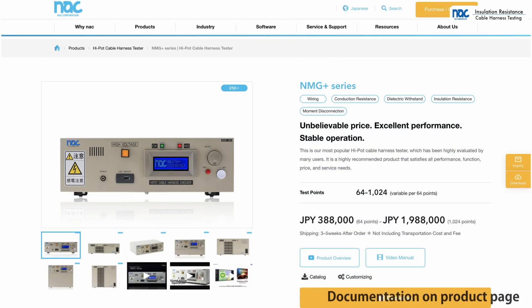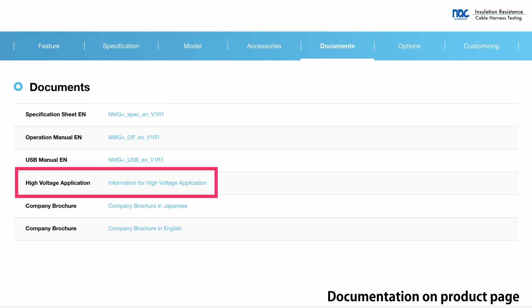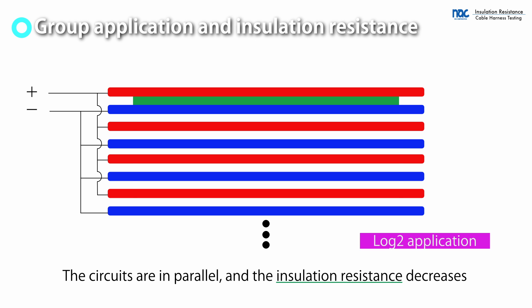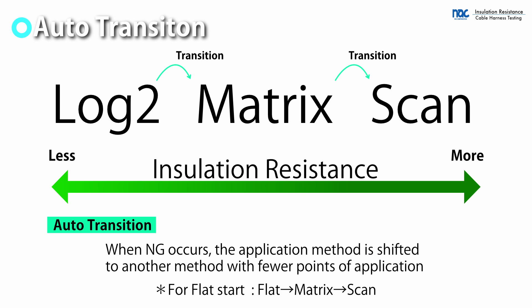The application table for each method can be downloaded from our website. Group application methods, such as Log2, complete the test in a short time. However, the leakage current value increases, making the test more severe. Auto-transition mode is helpful in this case. If the leakage current value exceeds the set value, the application method is automatically switched and the test continues.